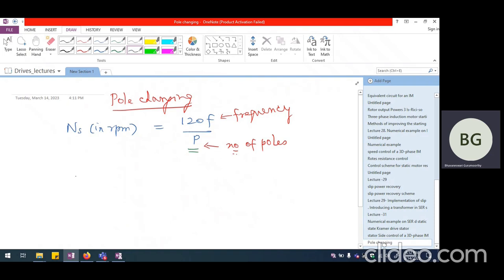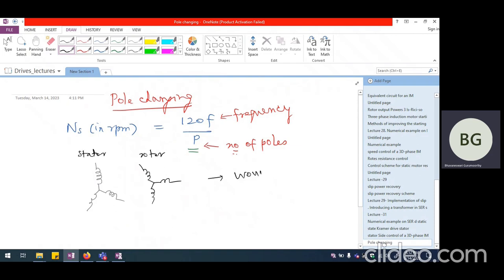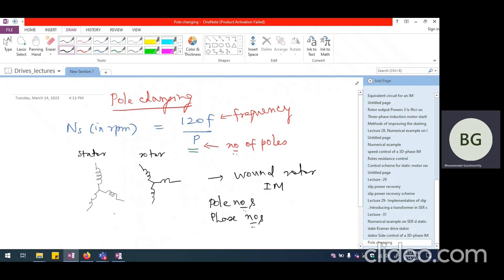In a wound rotor induction motor, the stator and rotor both have three-phase windings. The rotor and stator windings have to match each other in terms of pole numbers as well as phase numbers — if the stator is wound for four poles, the rotor must also be wound for four poles. So if we change the number of poles in the stator for pole changing, we necessarily need both stator and rotor windings wound for different numbers of poles, making it very complex.